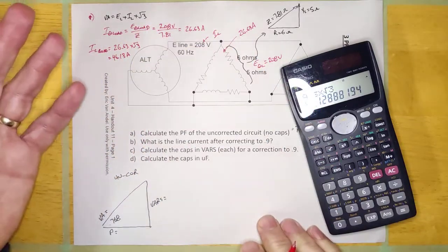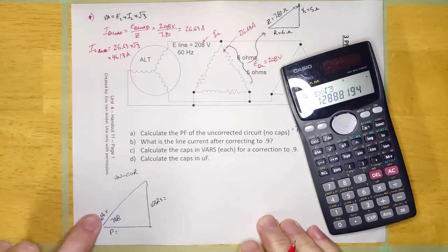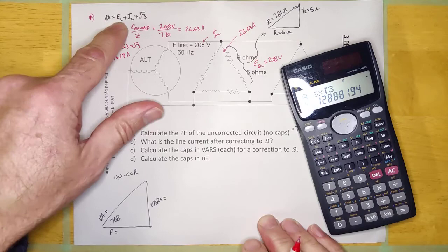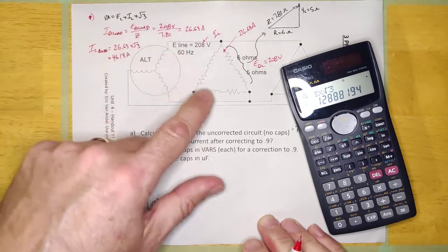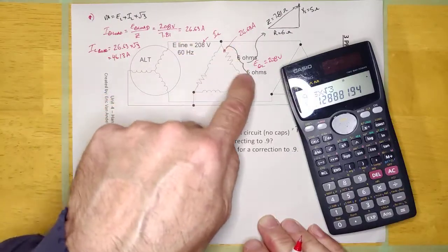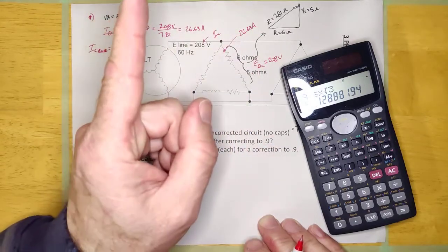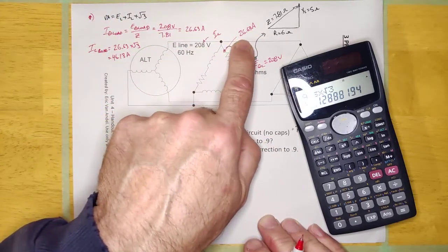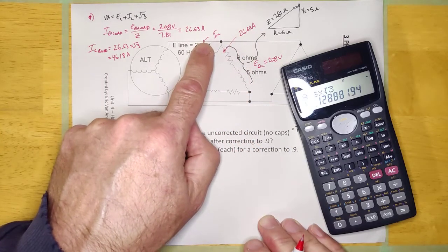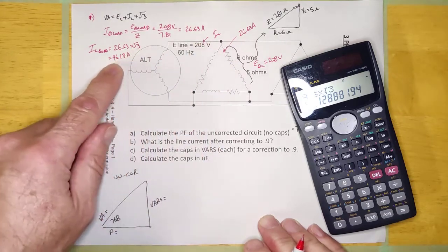Okay, so let's just review here. Our goal in life is to figure out the VA of this circuit, because if I have the VA and the power factor, I can finish this drawing, okay? The only way to calculate the VA is to know E line and I line, and I know E line, and I'm working on calculating I line, okay? Now, the only way to get I line is to figure out what the voltage dropping across that is, and then dividing it by the ohms of that. But you have to remember that what you've calculated there is I phase, okay? I have to take the extra step and make sure that I get I line, all right? And it's delta, so I multiplied it by root 3.